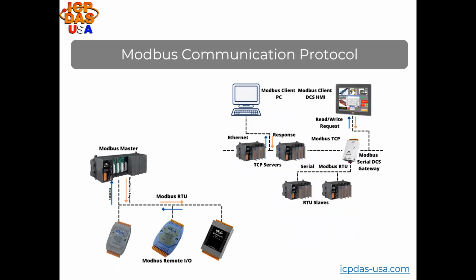Modbus is a communication protocol for transmitting data between devices over serial lines or Ethernet cabling. It's a master-slave protocol where a master device controls the transactions with slave devices that respond to requests to read or write data. Modbus is often used to connect PLCs or PCs running SCADA software to I/O and instrumentation equipment for automation, monitoring, and control applications. Data is exchanged through 16-bit registers. It's up to the master, which is the controller or PC, to request and use the data.